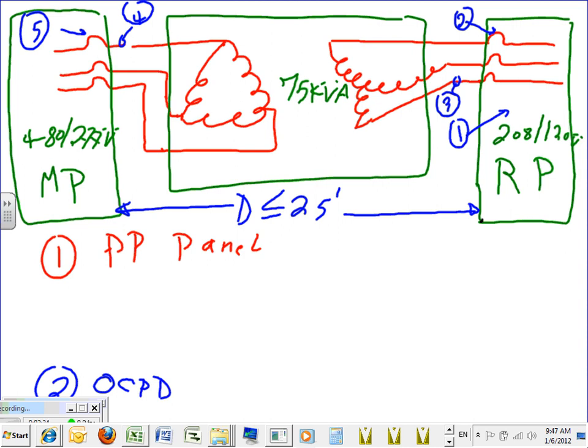The main panel and the secondary panel must be no more than 25 feet apart - otherwise you have to do a different analysis. Most of the time what we do is have the 480/277V panel on one wall, the transformer sitting on the floor, and the 208/120V panel right there. You grab the feeder from the 480 panel into the transformer and out to the other panel. Typically 25 feet is the tap rule we use with a transformer.